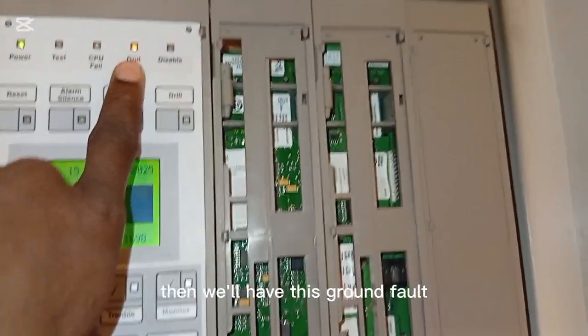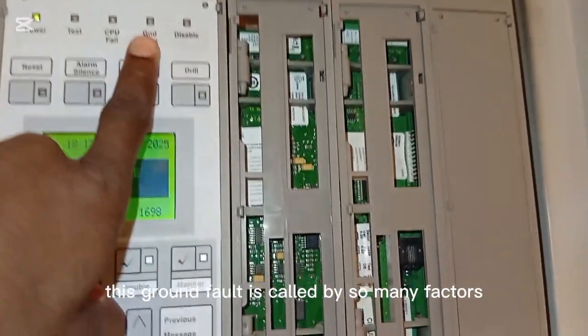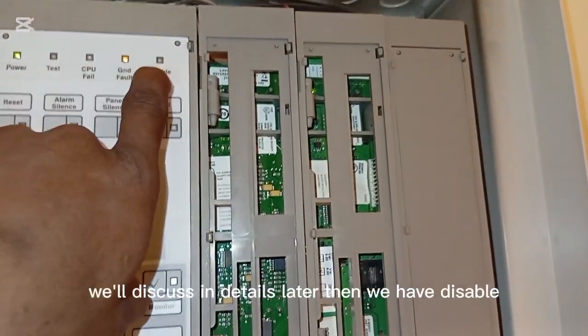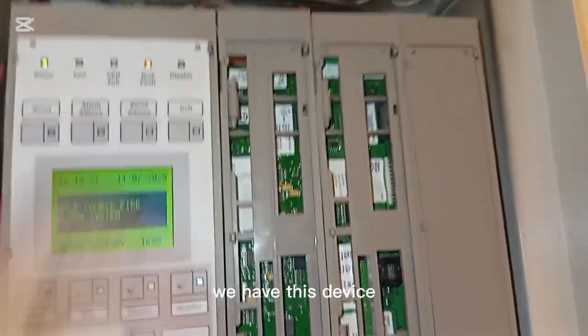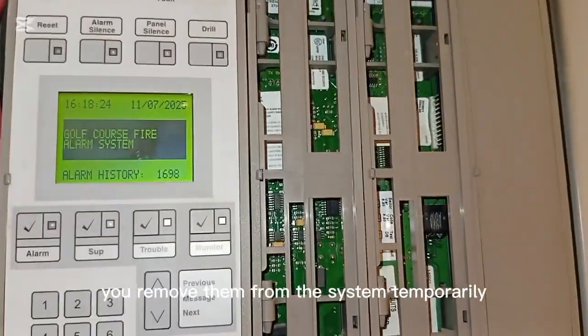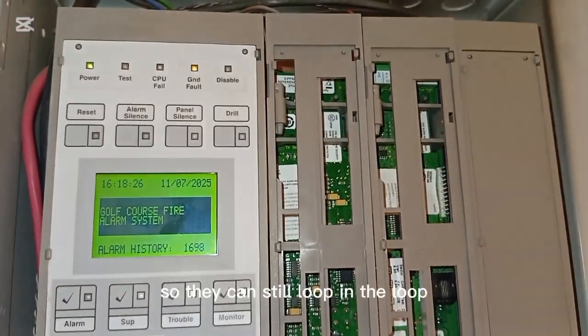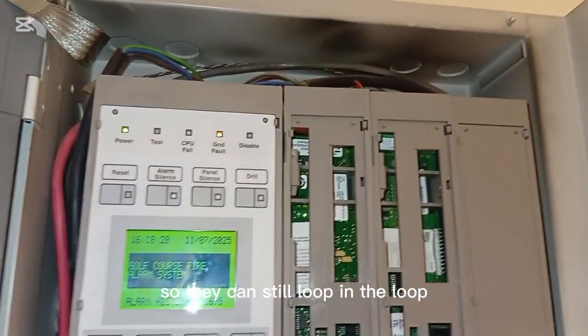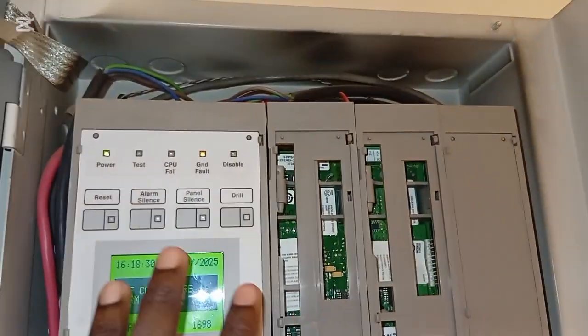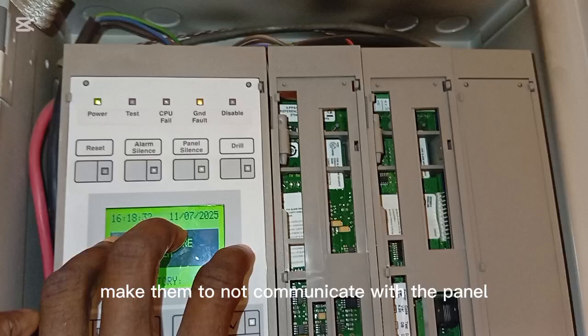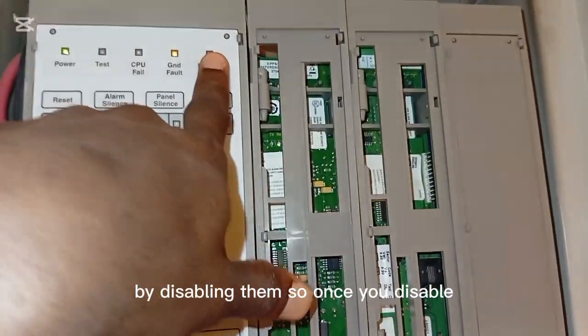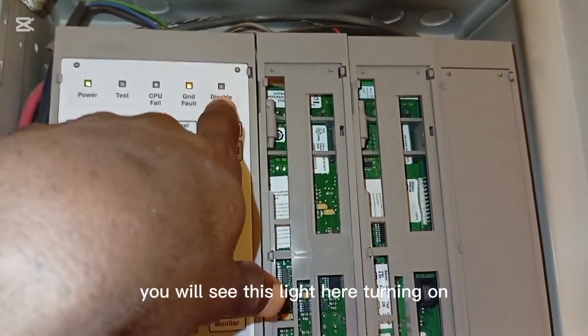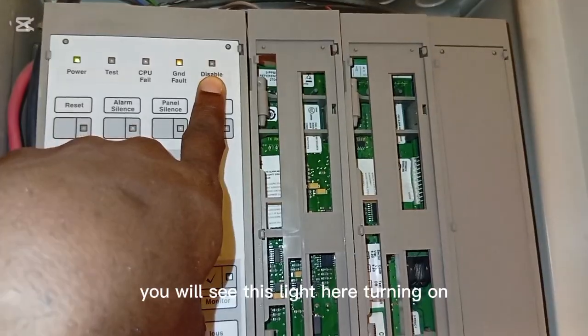Then we have this ground fault. This ground fault is caused by so many factors. We'll discuss in details later. Then we have disable. You can remove devices from the system temporarily. They can still be in the loop, but you can make them not communicate with the panel by disabling them. So once you disable, you will see this light here turning on.